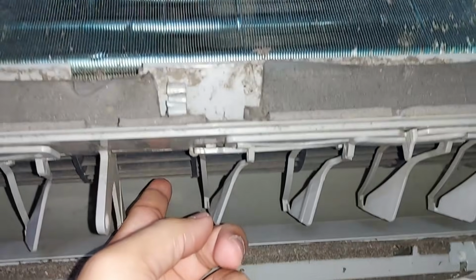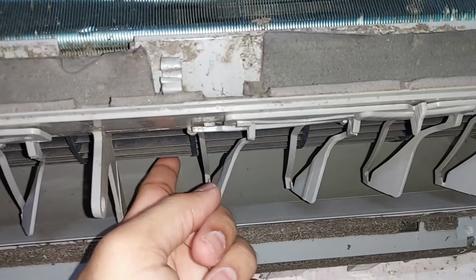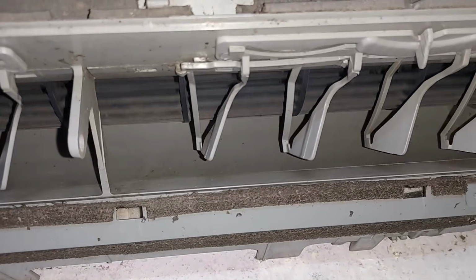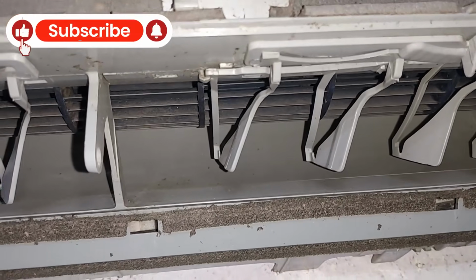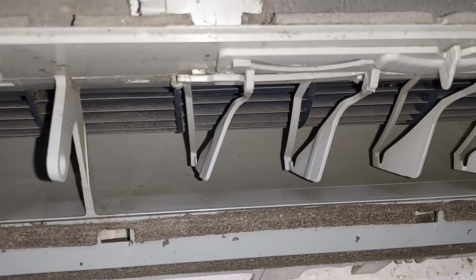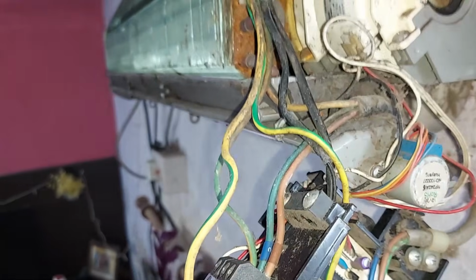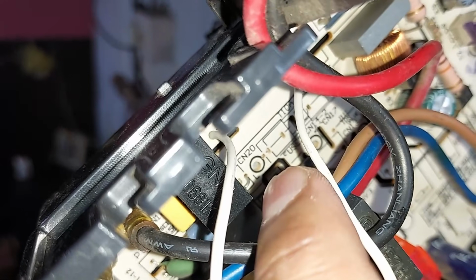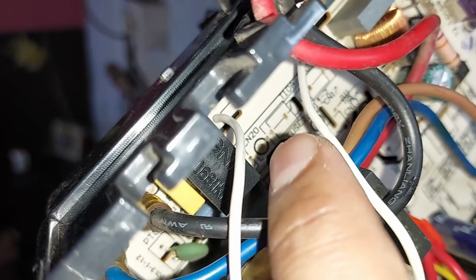First you just spin it with your hand, and if it rotates smoothly, that means the mechanical part of the motor is fine. Then you've got to check the electrical part, and the most important part is the capacitor, which stays right here.